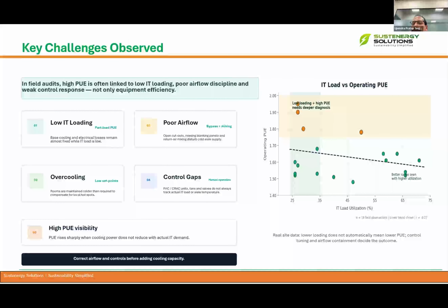So the idea is that first we need to reduce the avoidable cooling energy, then we need to protect the rack inlet temperature and redundancy, and then convert the savings into verified carbon reductions. That is the roadmap we need to follow. The idea is not just to add some cooling capacity or add additional PACs, etc. First we need to optimize the cooling. Then we need to add capacity when we find a reliability gap. Reliability gap means we need to know how many kilowatts is the IT load and how much is the cooling load. Then we need to consider what redundancy level we are looking at. And then we can decide whether the existing cooling capacity is sufficient or not, or should we go for any addition of units.